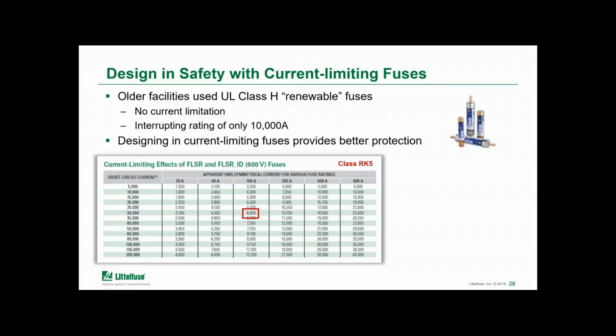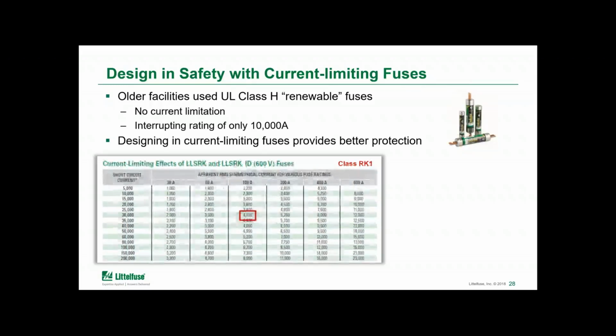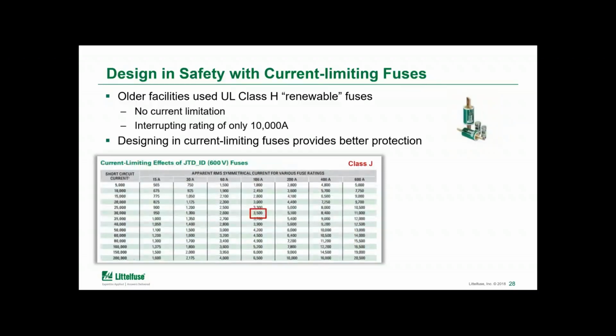So let's say that the fault current on our fusible disconnect was 30,000 amps. A 100 amp class RK5 would limit that current down to 6,400 amps. Now, if you look at another fuse that's physically the same size, but designated to be more current limiting, the RK1, you could bring that down to 4,100 amps. And again, looking at class J, you could lower that even further to 3,500 amps.